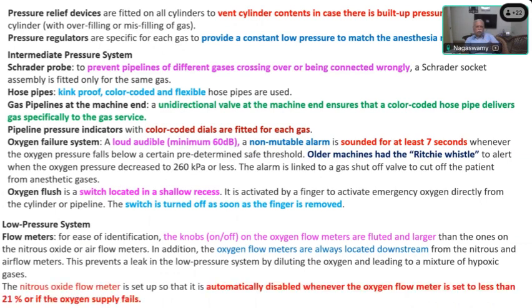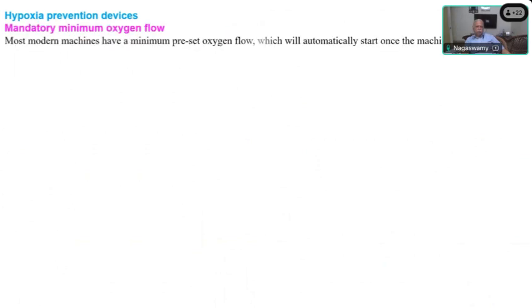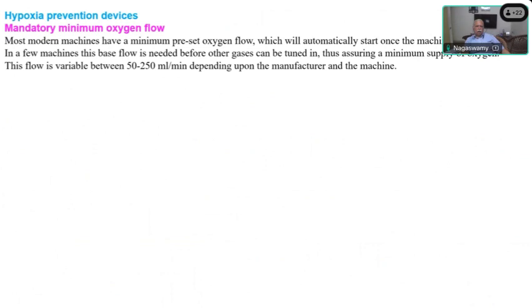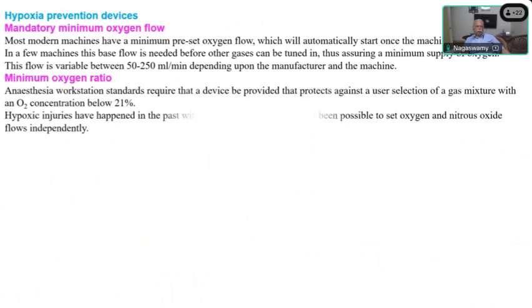And how these flow meters are activated and how hypoxia is prevented. So, hypoxia prevention, which you mentioned: minimum mandatory oxygen flow. Most of the machines have a minimum mandatory oxygen flow of 50 to 250 ml per minute, depending upon the manufacturer. And there is a minimum oxygen ratio to give at least 21% to prevent hypoxia.